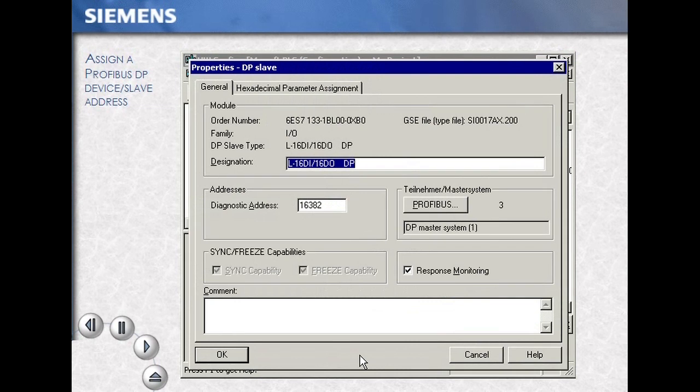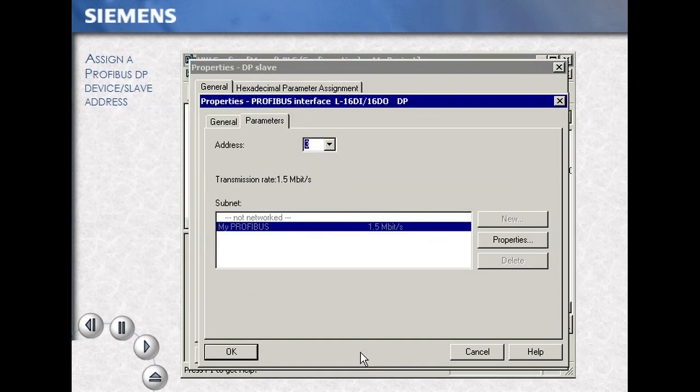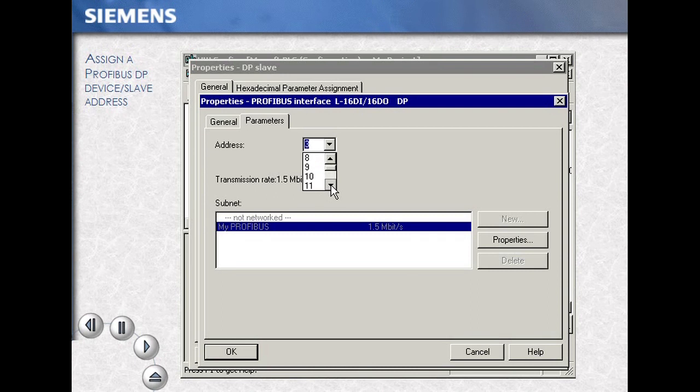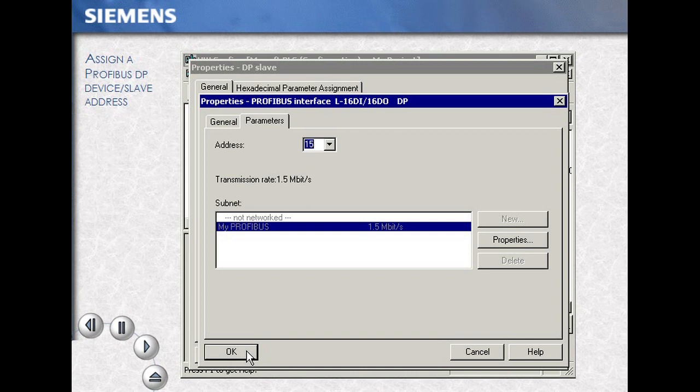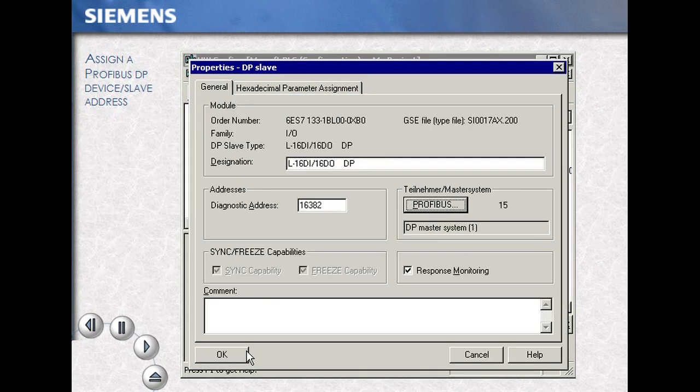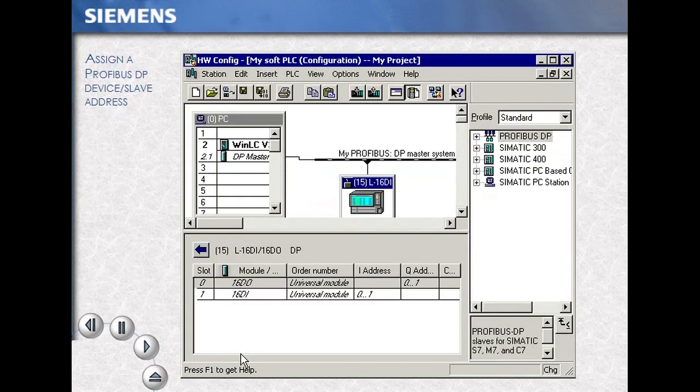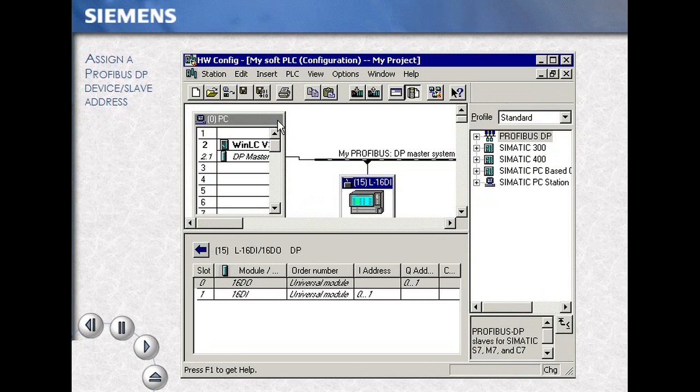Click on the Profibus button, then either scroll through the menu and select the address of choice or type in the address. OK your selection and OK to confirm. The address has been changed. Save and compile your work.